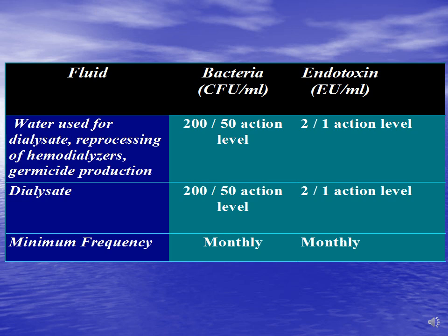It's actually a medical assessment whether or not you continue dialysis with a report of 200 CFU or greater, because the physician has to assess which is more detrimental: withholding treatment on a patient with high lab results, or subjecting them to dialysis with a bacterial count of 200, knowing that the dialyzer membrane is capable of filtering out or blocking that kind of contaminant from reaching the patient's blood. So it's a medical assessment call. It's not an automatic stop dialysis.